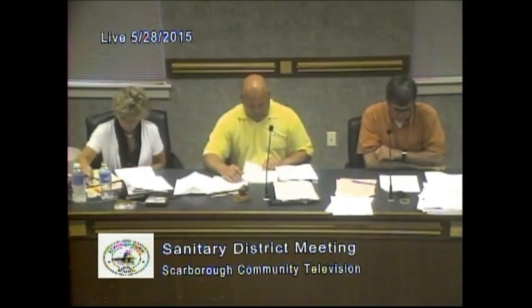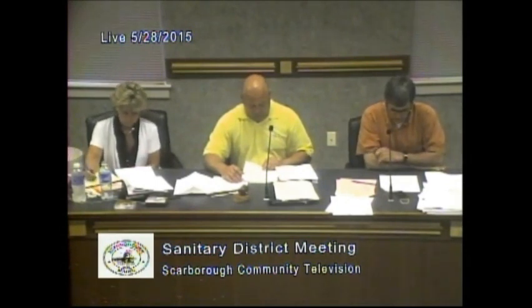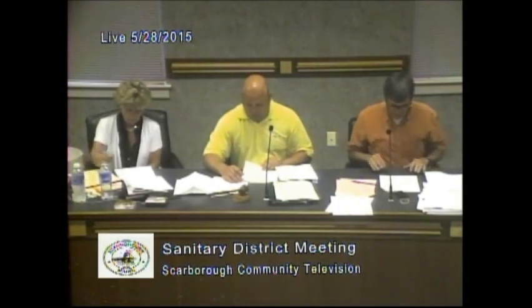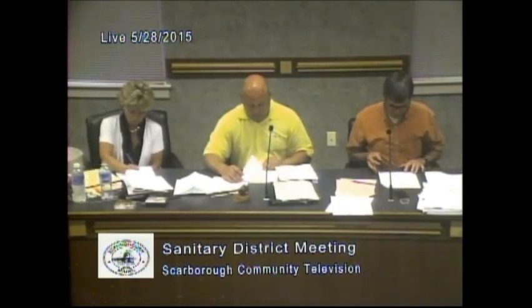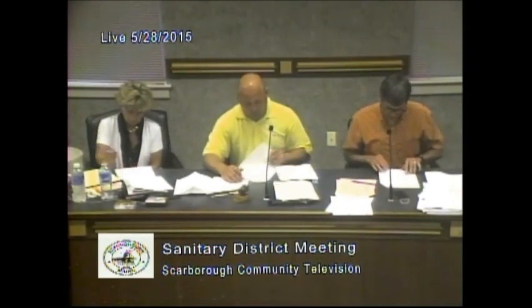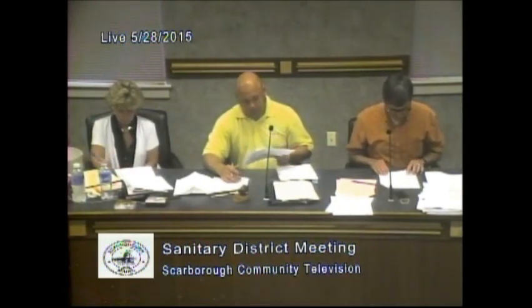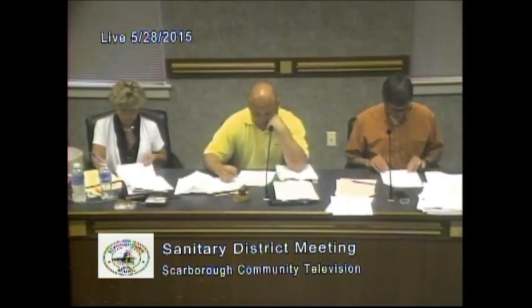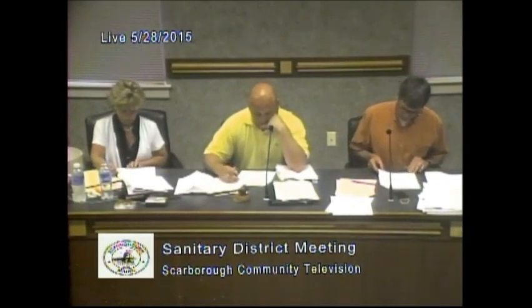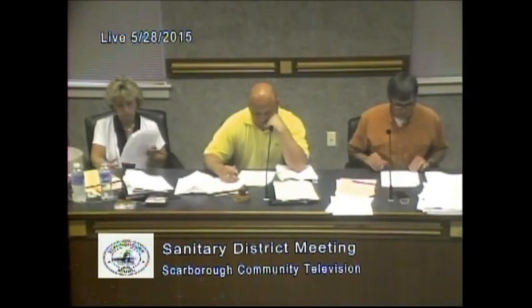All gravity sewers shall have detectable underground utility marking tape placed approximately 3 feet below grade, directly above. The pump station control panel shall be replaced. Remote communication of alarms, including loss of commercial power, to the on-call service provider shall be included as part of the new panel. The panel's functionality shall be fully maintained at all times. Final plan shall be amended in accordance with district standards, signed and stamped by a licensed professional engineer, and submitted to the superintendent for approval prior to issuance of permits.